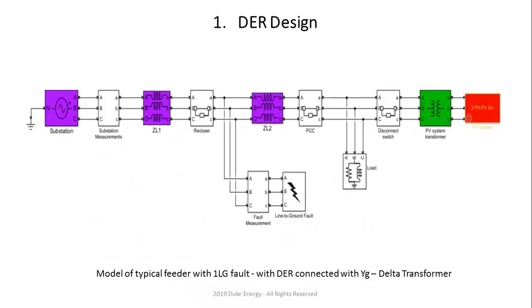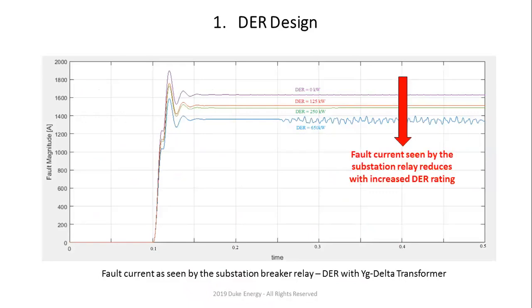So the transformer that you see on the right side in green is Y grounded delta. This is probably, for some reason, the most common configuration that you can see in a lot of papers and simulations. And I'm going to show you why that is not the preferred way to do things, especially when you tie it to the distribution feeder, right? So we tied the PV inverter through the Y grounded delta transformer, and you can clearly see that as the DER size increases, the fault current seen by the substation relay reduces with the increased DER rating. So that means the higher the PV, the lower the fault current magnitude that is going to be seen by the relay in the substation. This is for a Y grounded delta transformer at the PV site or any DER site, right?